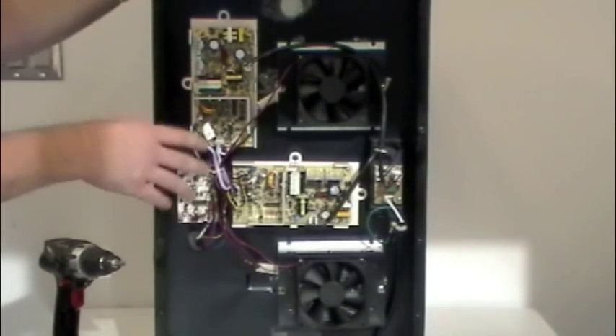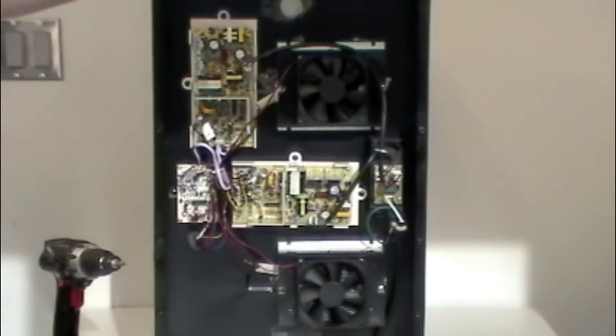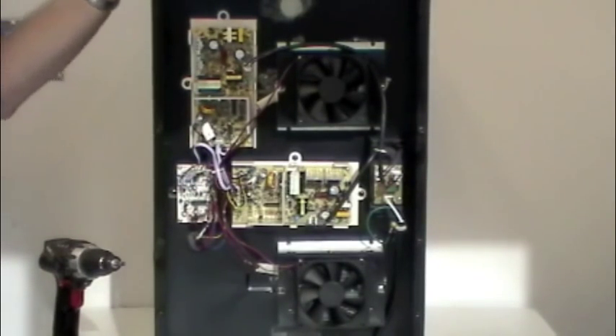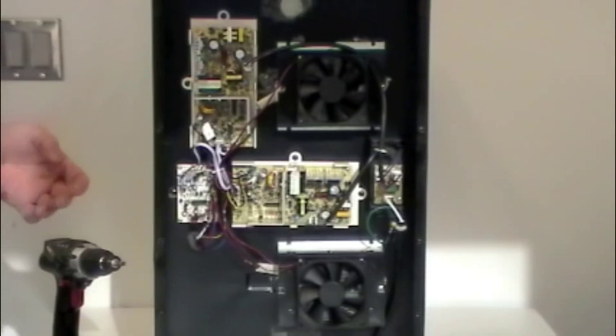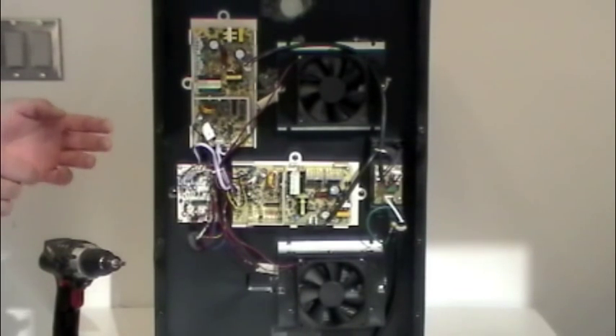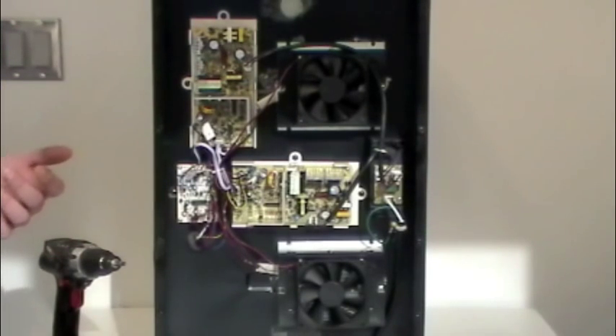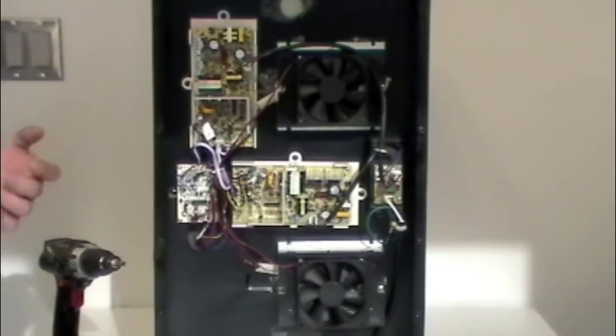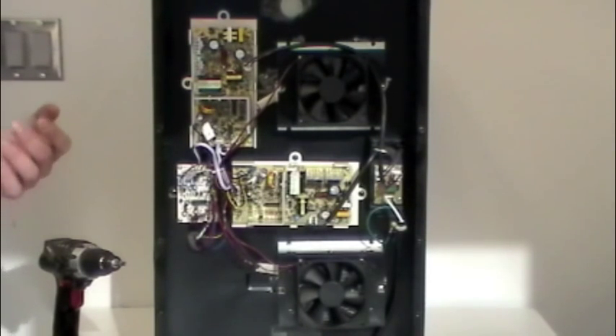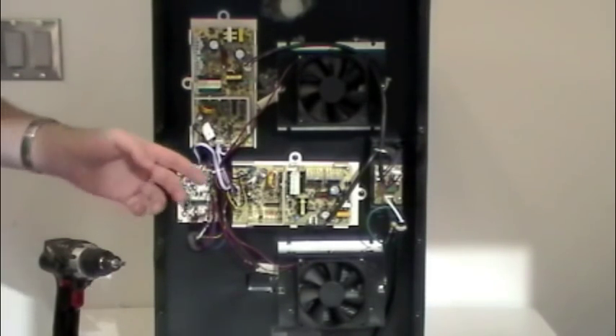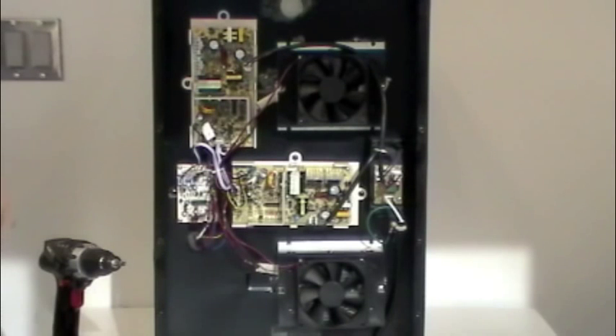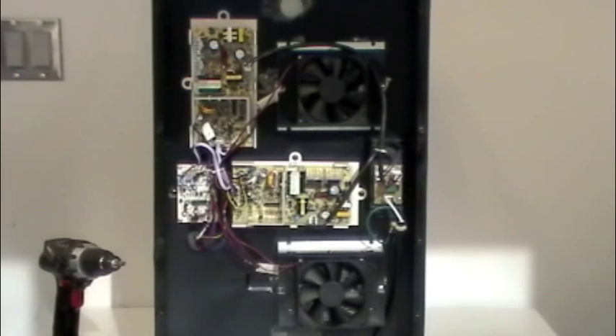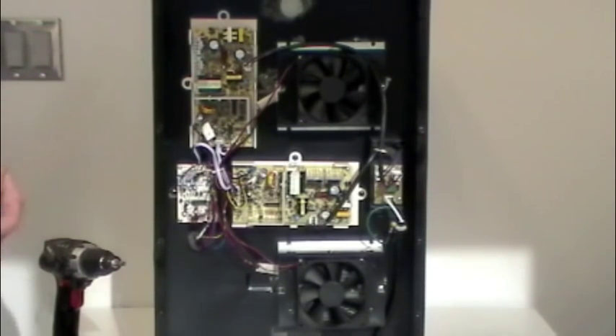If you see any kind of indication in here where something's wrong. Let's say, for example, both lights have a fast flash. We know that the switching part of the board is probably defective. Because when those lights come on, it's trying to switch power to the other side of the board to get that board started. But then we lose something in that process. We have a defective component. So it gets into this continuous kind of loop. We're going to start, stop, start, stop. And that's where we get that flash at. Or the other situation, which is fairly rare, is that we would get no red indicator light at all. The green light may flash a little bit or be on really weak or really dim. If you see any of that, odds are it's a circuit board. Again, those LEDs are a pretty good telltale. They're not 100% accurate, but for general purposes, we would use those to diagnose the board. And that's really our only window into what the board is doing.